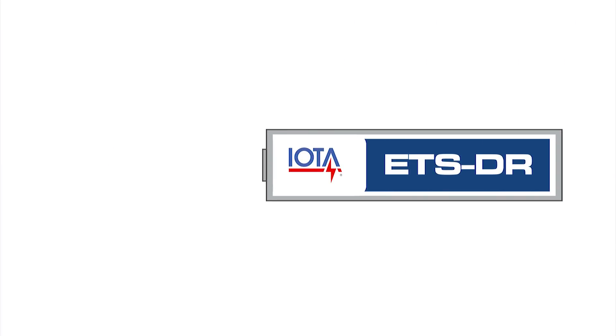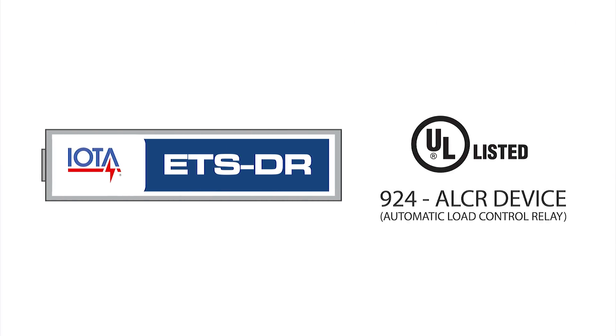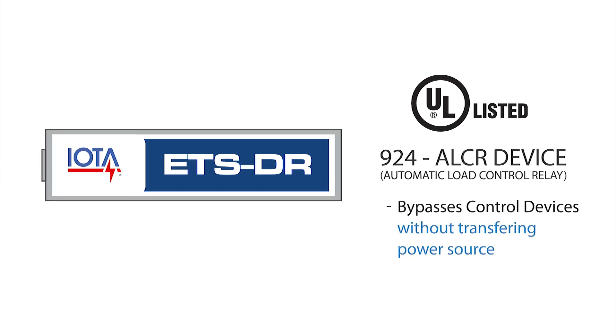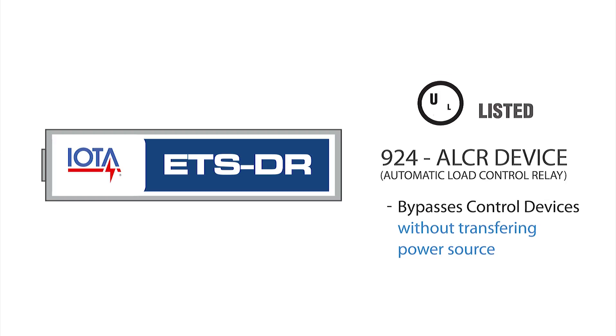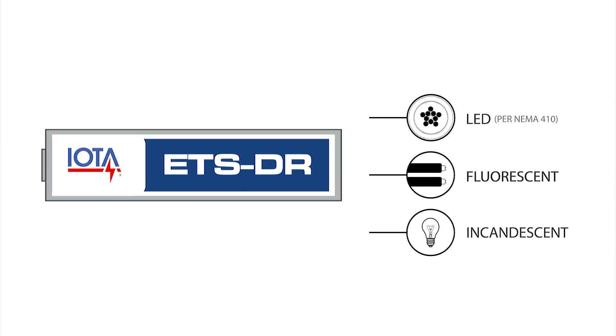The ETSDR is UL924 listed as an automatic load control relay device that will bypass control devices without transferring power between the normal and emergency source. The ETSDR is also rated for any lamp load up to 3 amps, including LED loads per NEMA 410 standard.